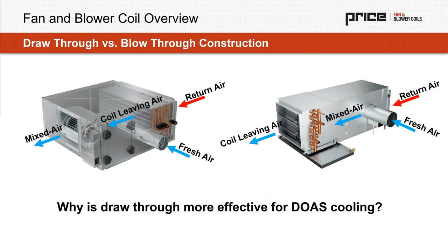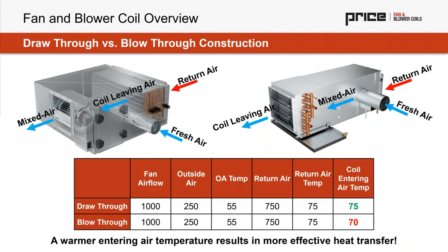As the fluid temperatures approach one another, there's less potential for heat transfer. So the larger we can make that difference between water side and air side temperatures, the more efficient our heat transfer will be. And the easiest way to look at this is just by applying a few numbers to it. In this case, we have our fan set to supply 1000 CFM in both cases.